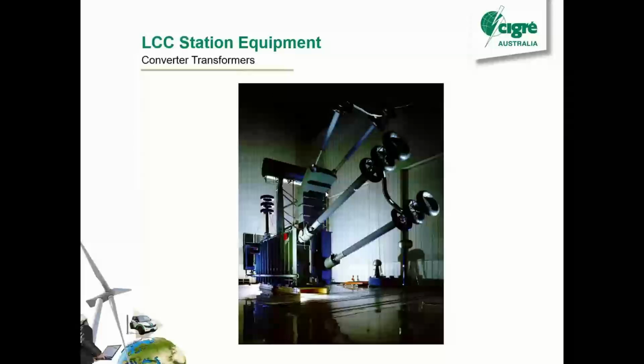Converter transformers. This picture is of a particularly large one. I think this is from an 800 kV scheme. You can see those bushings are extremely long. There's no way this transformer would pass the seismic requirements for New Zealand, so I don't think we could ever have one here, but in a non-seismically active area, you might be okay.